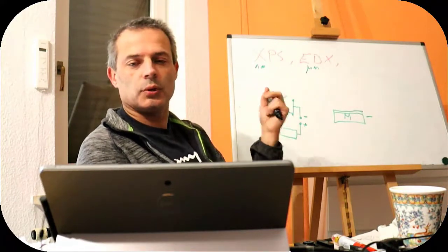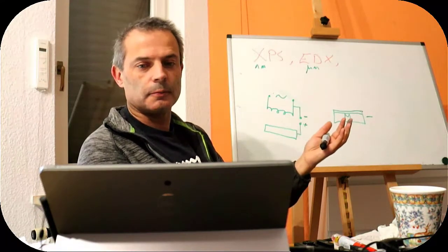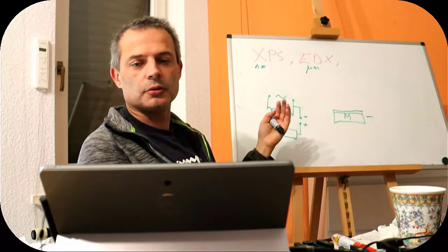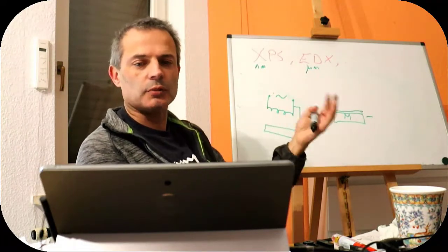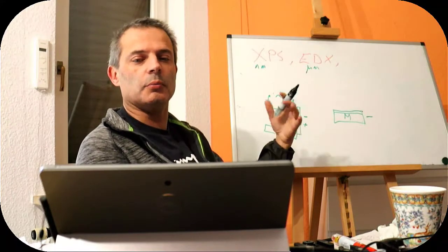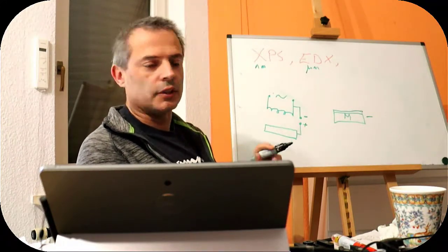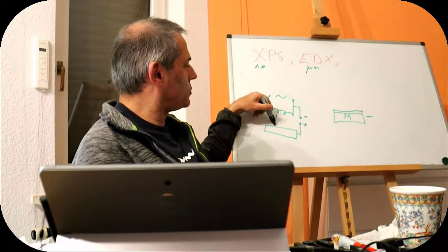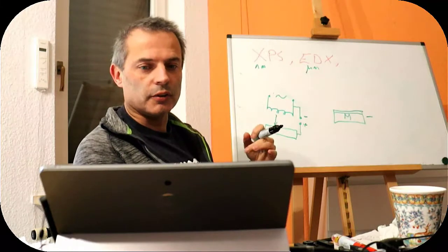For X-rays we need quite a lot of electrons in the first place, and so we can't do it like that. To generate a lot of electrons, it's better to have a hot filament because it makes more electrons. And we can then make the whole of the filament emit electrons rather than just a point. This is a bad configuration because obviously our electrons will come straight into this positive electrode, and that is not going to be very good.